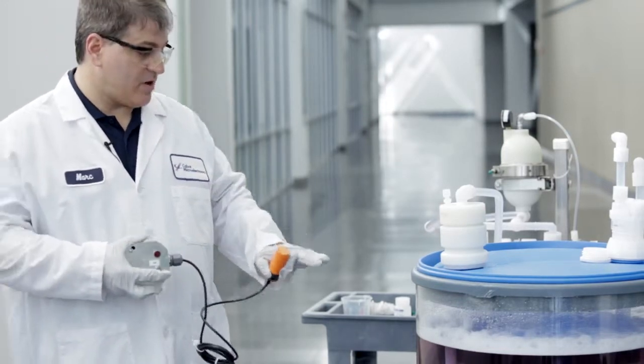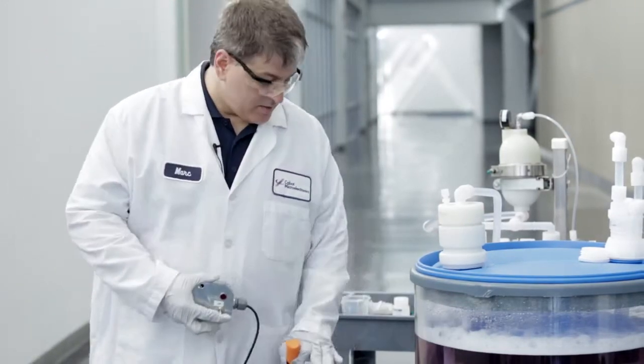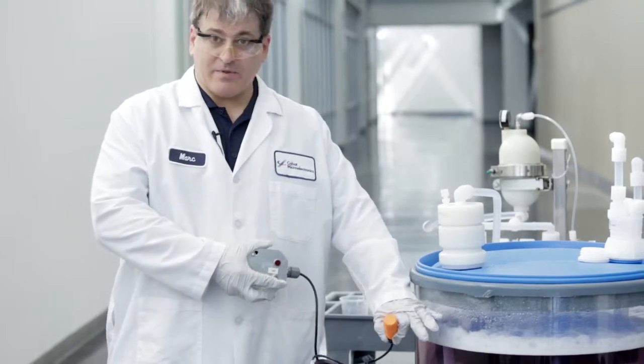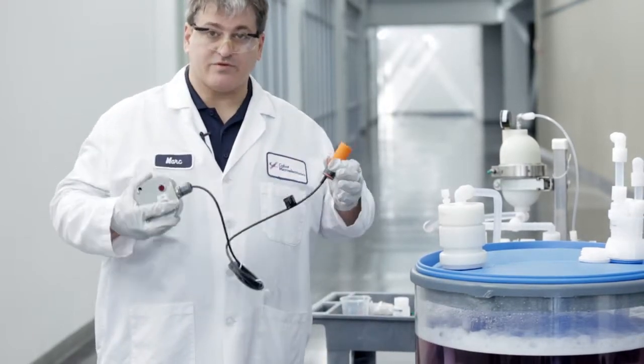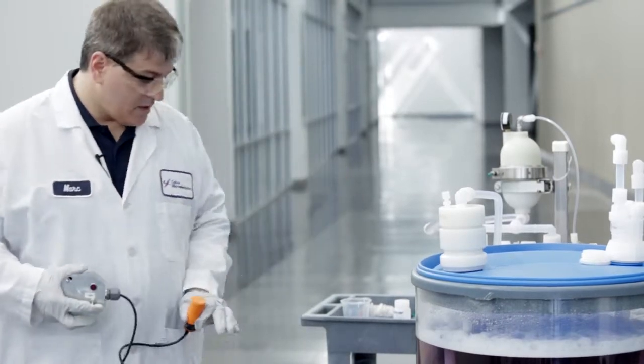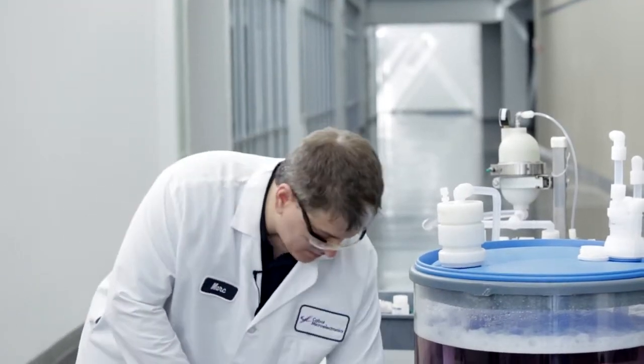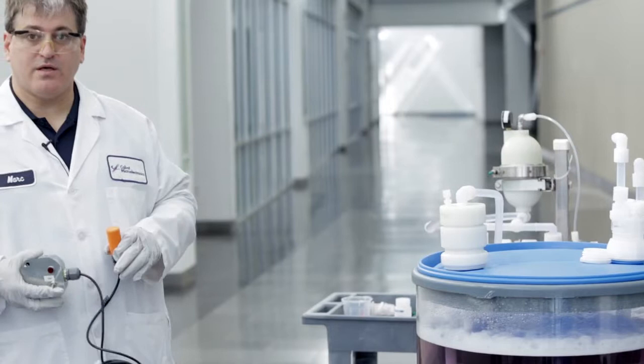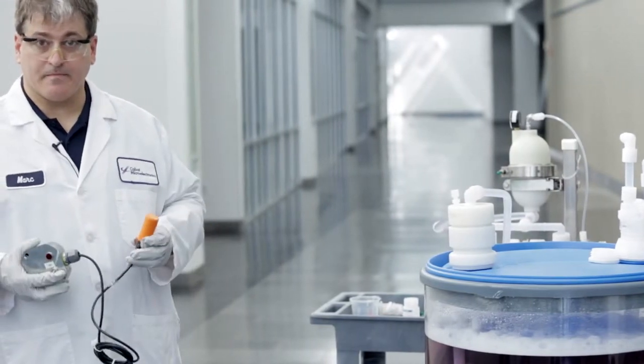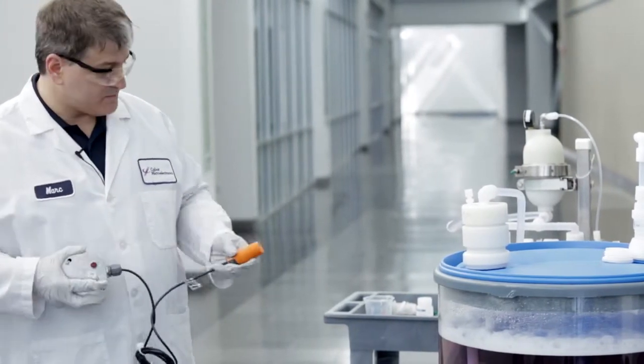And this can result in artificially high readings if the foam is present at the top of the tank, and it can set off over-level sensors or overflow sensors. At the bottom of the tank, you can run out of slurry and the foam is still present, and you could starve your system. Either one of these is to be avoided.